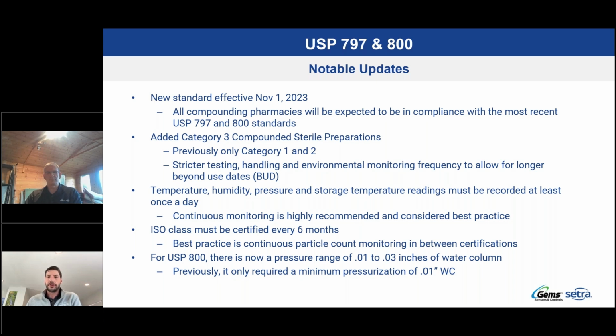However, continuous monitoring is highly recommended and considered the best practice. You also have to have your clean room certified either annually or biannually, depending on the ISO class. And one other change that took effect with the latest regulation is that there's now a pressure range for your USP 800 areas. Before, it just had to be larger. You just had to have a minimum of 0.01 inches of water column. Now there's a range of between 0.01 to 0.03 inches of water column. So it's good to have a continuous sensor measuring that and then alerting if you go outside of that range.